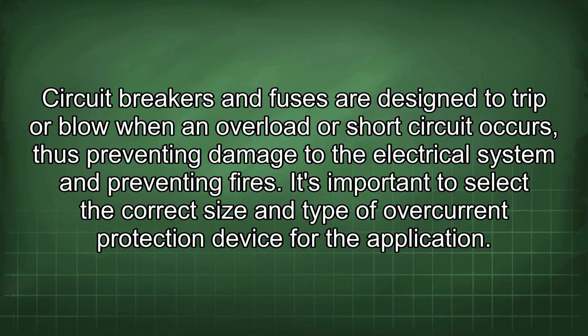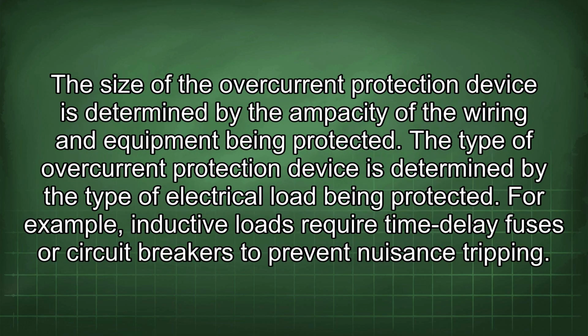It's important to select the correct size and type of overcurrent protection device for the application. The size of the overcurrent protection device is determined by the ampacity of the wiring and equipment being protected. The type of overcurrent protection device is determined by the type of electrical load being protected. For example, inductive loads require time delay fuses or circuit breakers to prevent nuisance tripping.